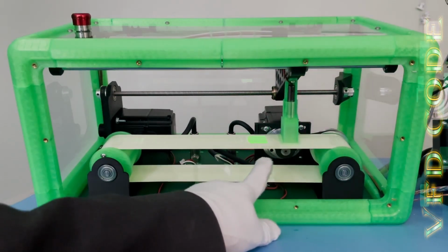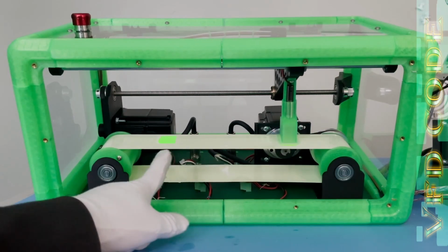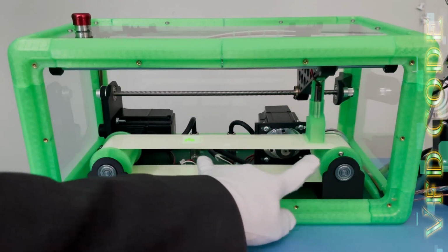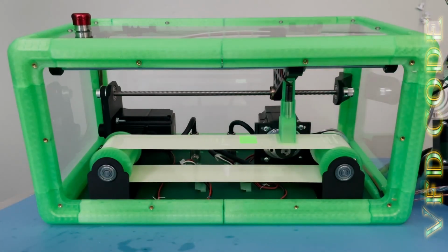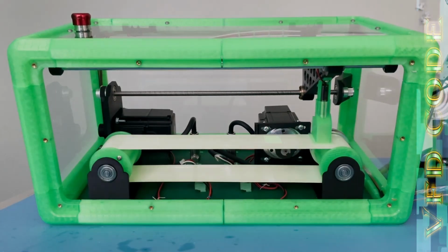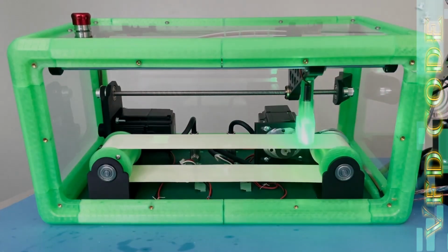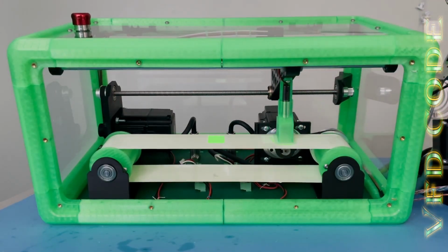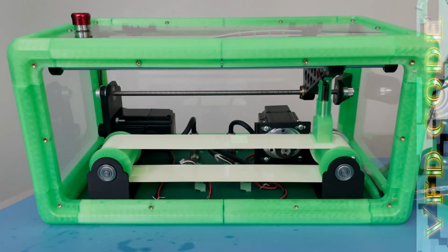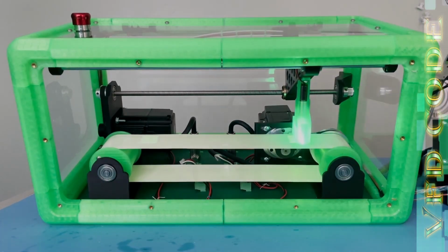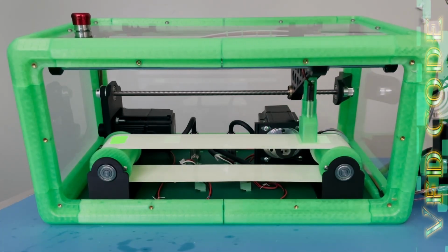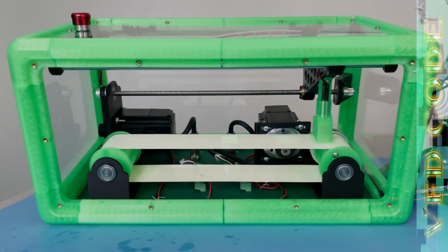And that is because the knife is not synchronized to the conveyor belt anymore, and it's also cutting the distance wrong. And that's because it doesn't actually understand the relationship between the conveyor and the knife anymore because I messed up the units inside of the software. Now, you don't have to worry about the units so much. We're not going to talk about it in this video because I covered it in an earlier video on how to set up user units. If you don't know how to do that, please look at that particular video.